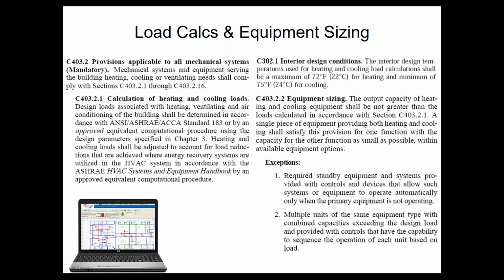However, if you have a package system with both heating and cooling, such as a rooftop unit, you are allowed to go a little bit bigger on either the heating or cooling in order to get enough BTUs on the other end of the scale. They recognize the fact that those are package systems. You can't dial in the exact heating and cooling, so you can upsize one or the other in order to make sure you get the minimum heating and cooling covered on the other side of the fence.